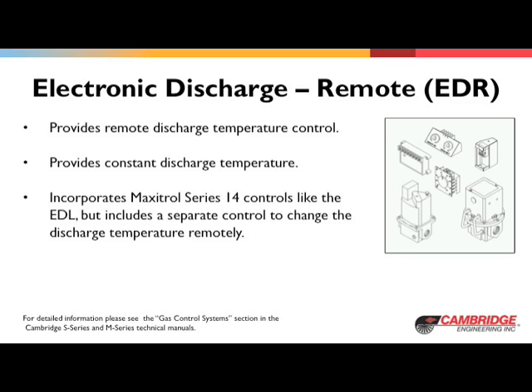The EDR incorporates Maxitrol 14 series controls like the EDL, but also includes a separate control to change the discharge temperature remotely. The EDR utilizes a Maxitrol A1014R1 amplifier, TS114 discharge temperature sensor, a TD114 adjuster, and either an MR212, an M511, or an M611 modulating valve.